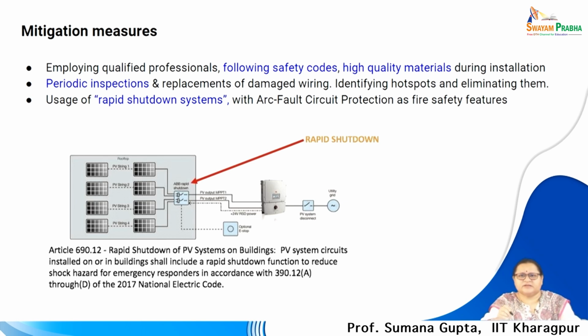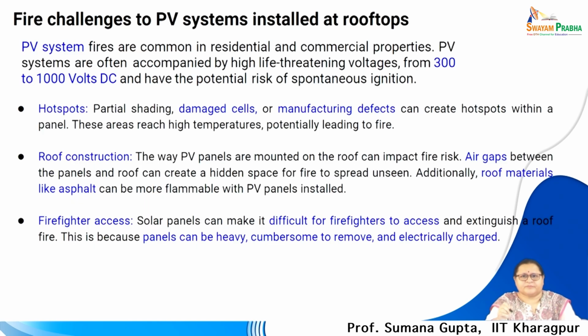So, this is how the mitigation measures work, and even if proper codes and standards for making all these are followed, there can be faults within the circuits, and that can lead to fire. So, these photovoltaic cells or systems are not one single unit, but a continuous whole, and they have DC voltages of 300 to 1000 volts and have the potential risk of spontaneous ignition. So, the hot spots where such kind of damage can happen will lead to a large scale facade fire.